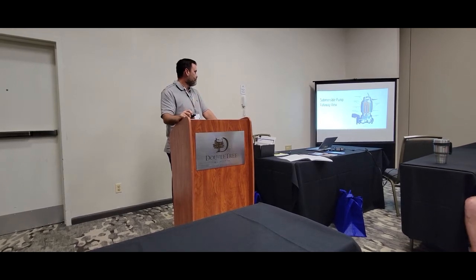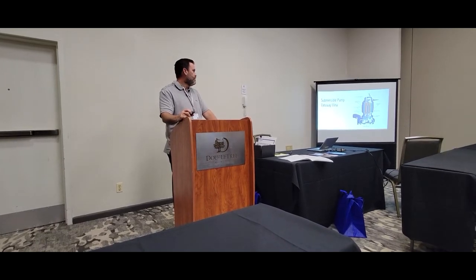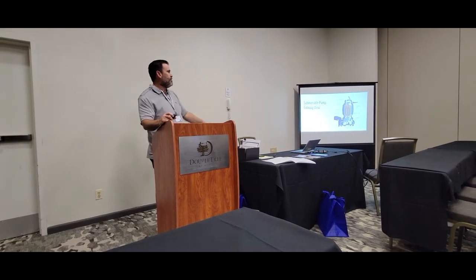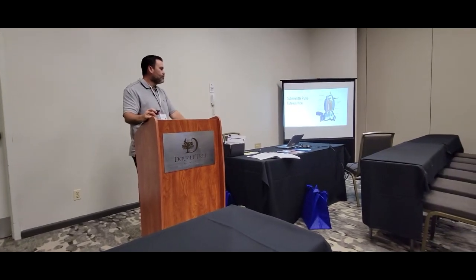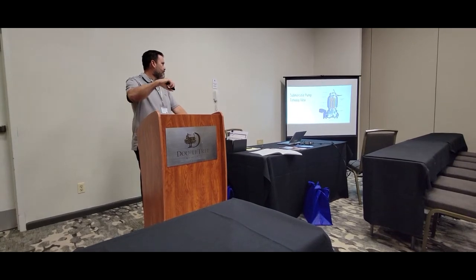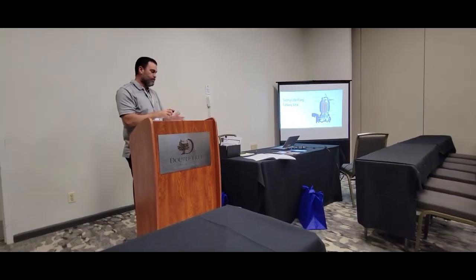This is a submersible pump. This is probably the most common that you're going to find in a lift station. Normally it's going to have a guide rail system where you can easily pull it out, maintenance the pump, unclog it, and slide it back down the rails where it's going to sit on a saddle. And basically the weight holds it down onto the gasket.